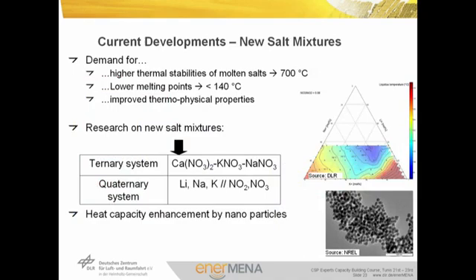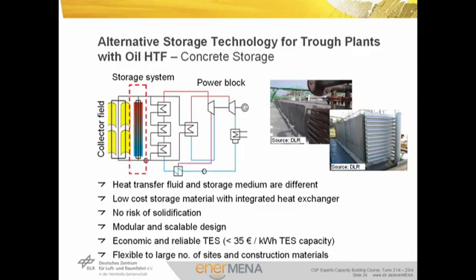Current developments in the area of two-tank molten salt storage focus on the identification of new salt mixtures. These salt mixtures should be cost-effective, able to be operated at temperatures of at least 700 degrees, and should show a lower melting point of less than 140 degrees. Research for these new systems focuses on ternary systems with three components and on systems with even more components. Another approach is the enhancement of heat capacity by addition of nanoparticles.